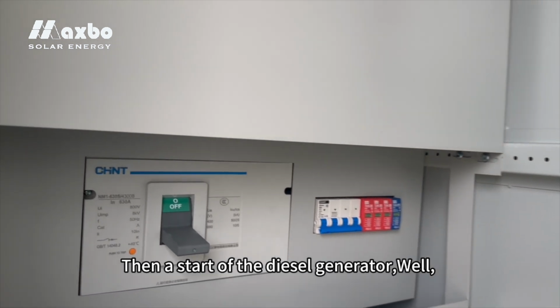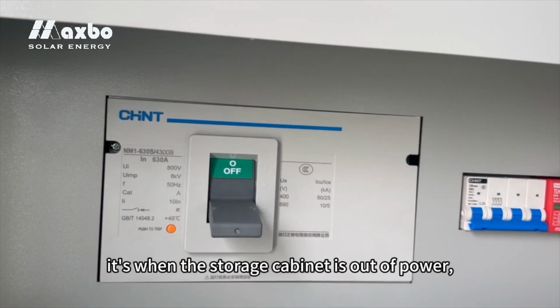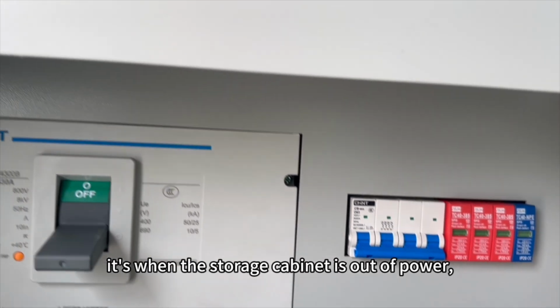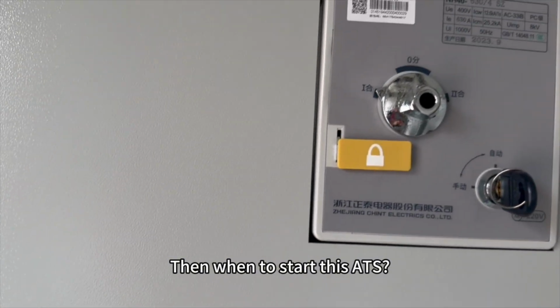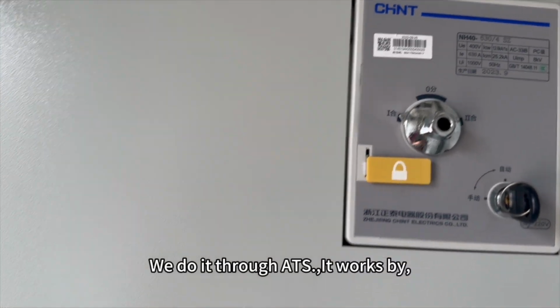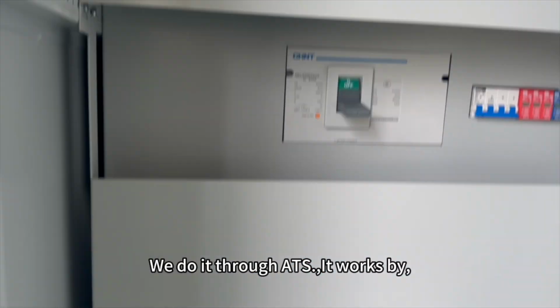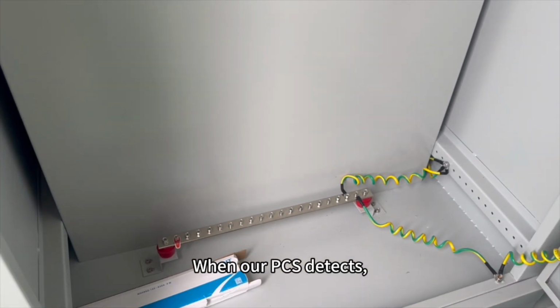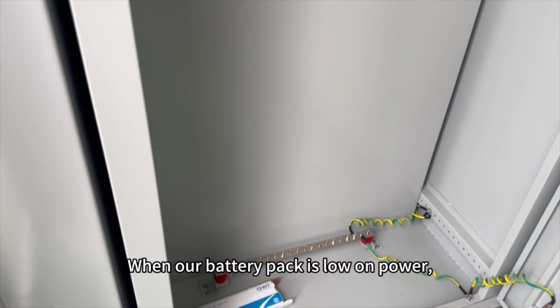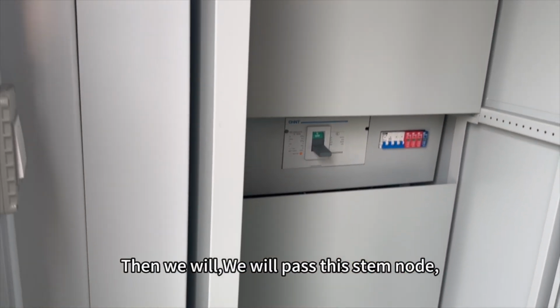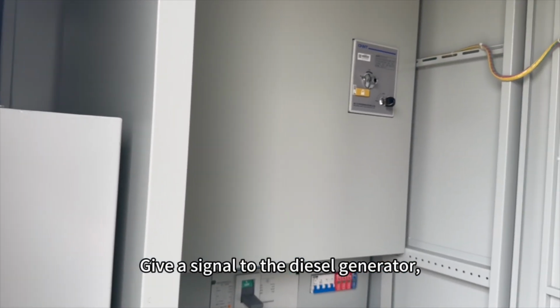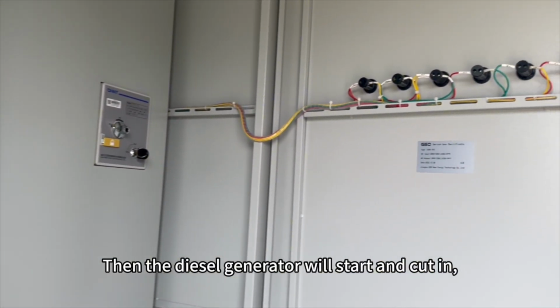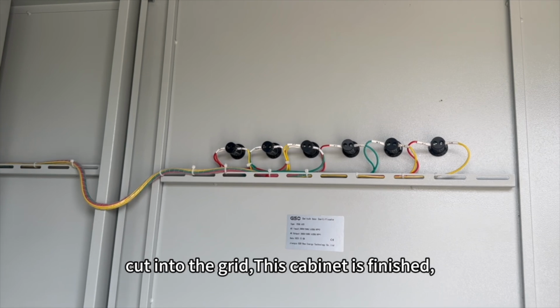Then the diesel generator starts when the storage cabinet is out of power, and we do the seamless switching through the ATS. It works like this: when our PCS detects that the battery pack is low on power, it sends a signal through this dry contact to the diesel generator, then the diesel generator starts and cuts into the grid.